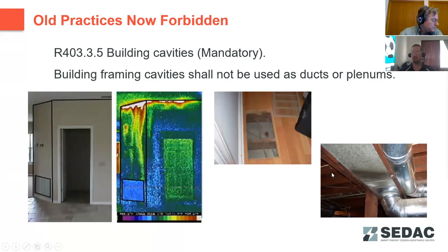Another thing, very important: you can put ductwork within a framing cavity, but you cannot use the cavity itself as the ductwork. So panned-in ducts, where a metal sheet's been nailed over top of a framing cavity, using that cavity as a duct, is no longer allowed. Again, the primary reason for that is it's very difficult to seal those properly, and you introduce a lot of impurities into that duct system with all the penetrations that go through that ductwork.